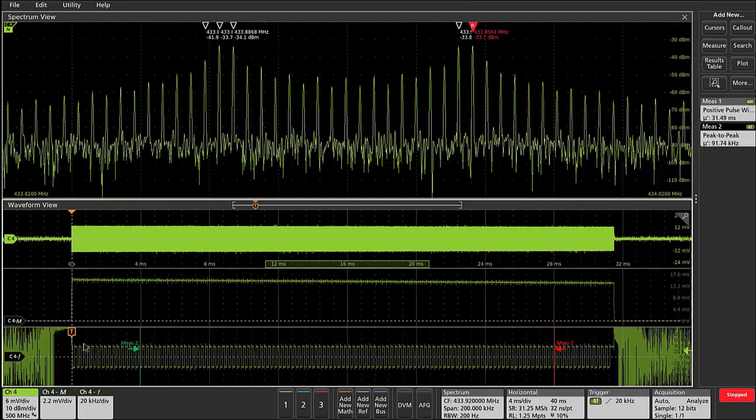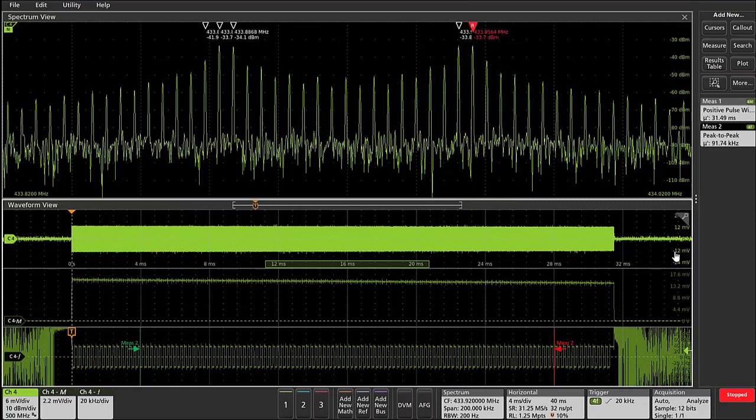Now we can see that the scope is triggering on and capturing the first place in which the frequency deviation waveform is changing by at least 20 kilohertz. So this is just one application area where the new RF versus time triggering capability of our scopes with spectrum view will be useful.